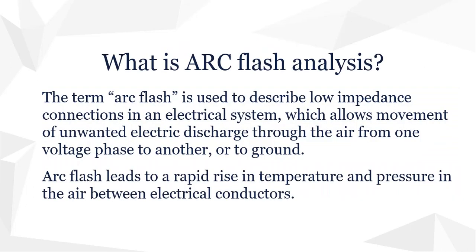The term arc flash is used to describe low-impedance connections in an electrical system, which allows movement of unwanted electric discharge through the air from one voltage phase to another, or to ground. Arc flash leads to a rapid rise in temperature and pressure in the air between electrical conductors.